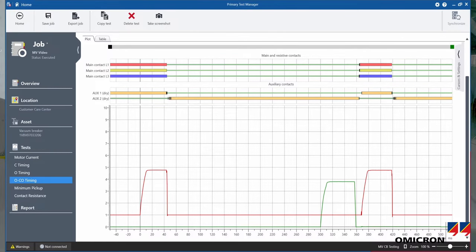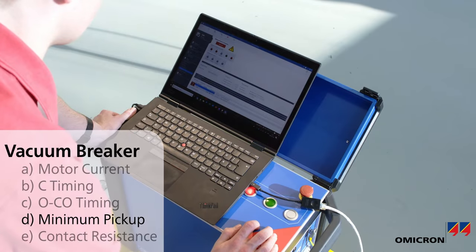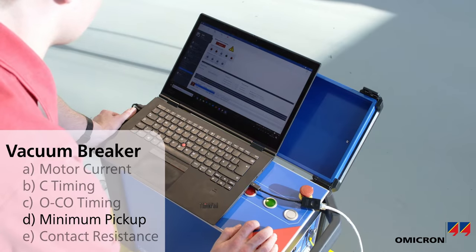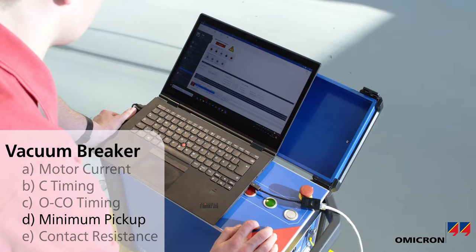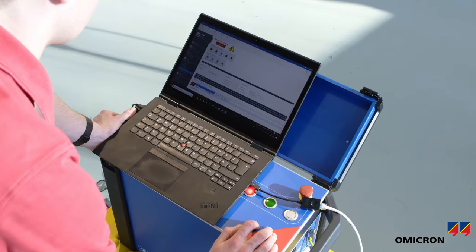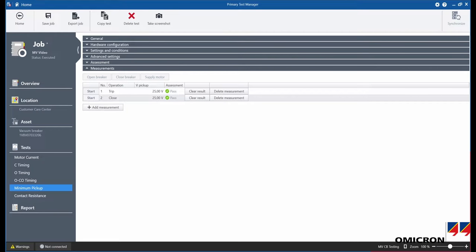In the minimum pickup test, a pulse ramp is applied to the coils to identify the minimum voltage that the coils need in order to operate.